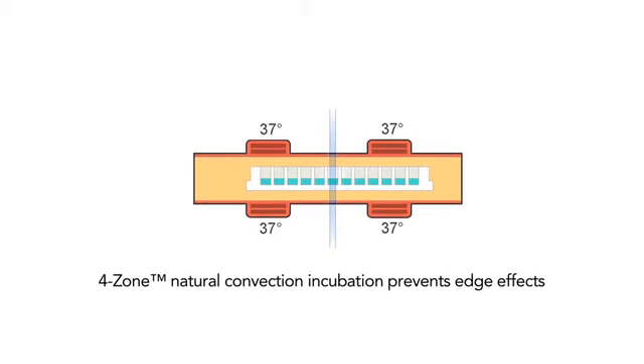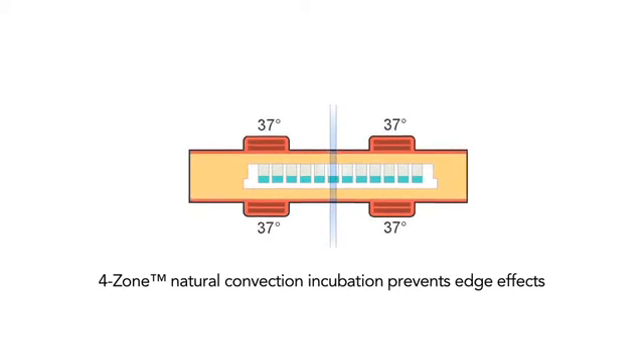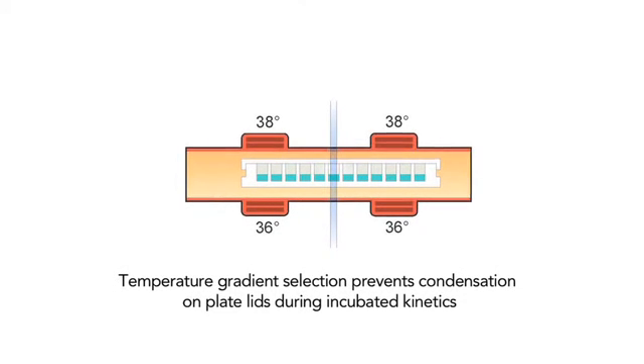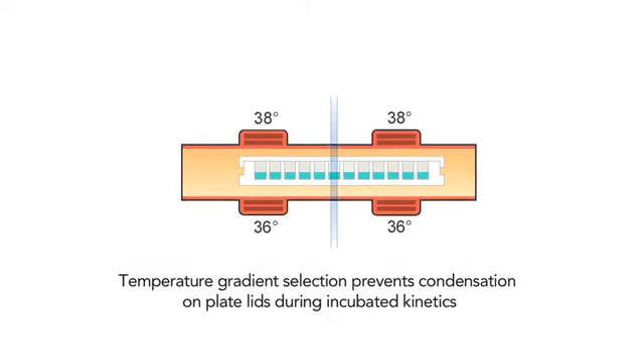For assays that require precise temperature control, its 4-zone incubation up to 65 degrees Celsius offers great uniformity across the plate and has a unique condensation control mode that's useful for long-term incubated kinetic runs with lidded plates.